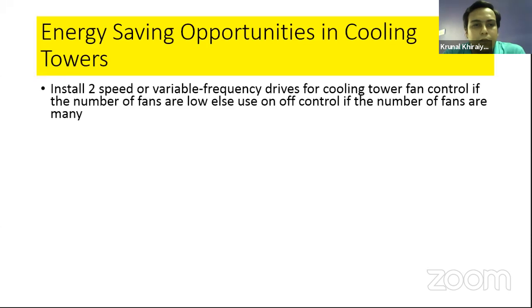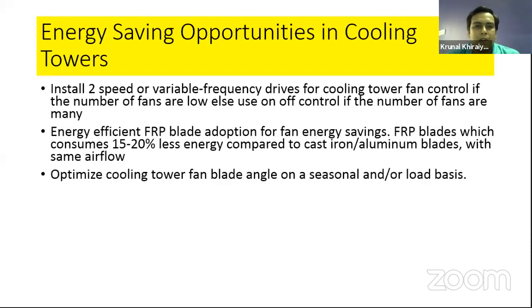Now, we go one by one. First, the energy saving opportunity in the cooling tower is to install 2 speeds. Yes, obviously it is in line with case study 2 that we saw. Second, in the olden days, we used aluminum or cast iron fans, means the blade of an axial flow fan made of cast iron or aluminum. But nowadays, people suggest using FRP because the blades come directly in contact with the water. So corrosion and erosion are there, and after some time you need to replace the blades. So we need to change the blade material, as FRP is a much lighter material compared to cast iron and aluminum. It helps us to save energy in the range of 15 to 20%.